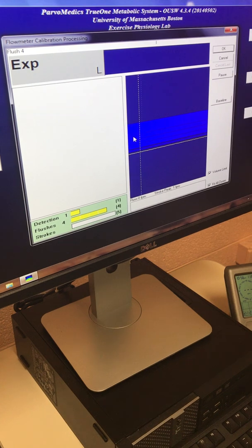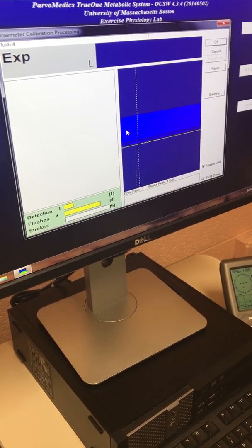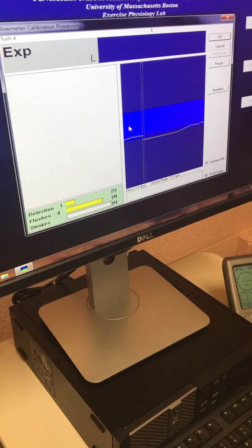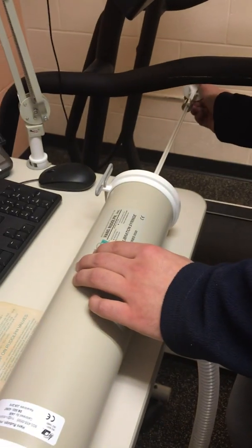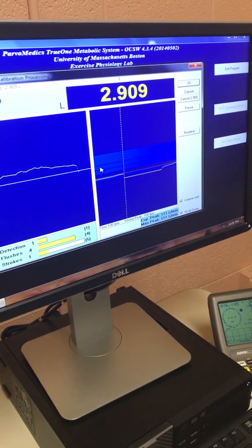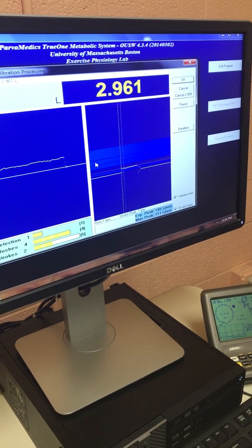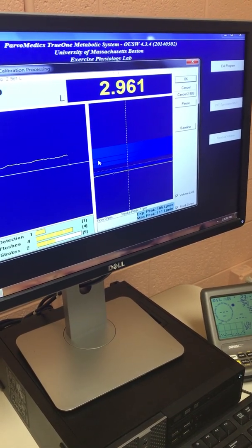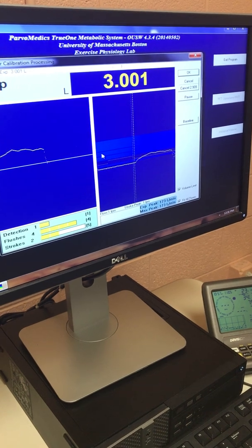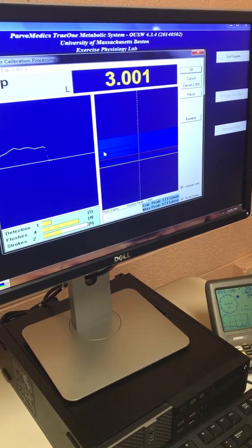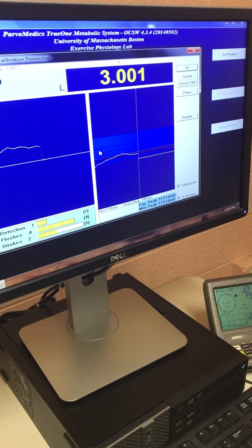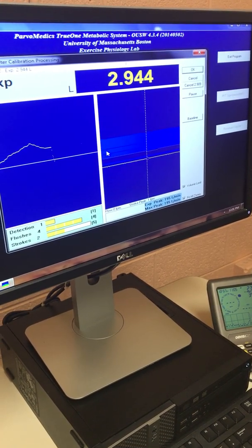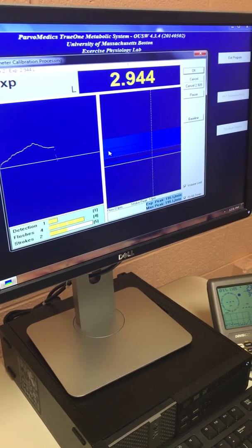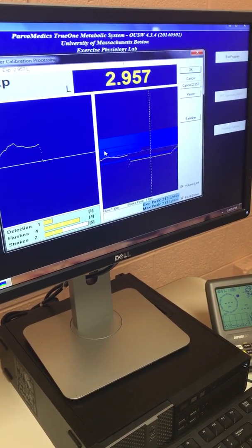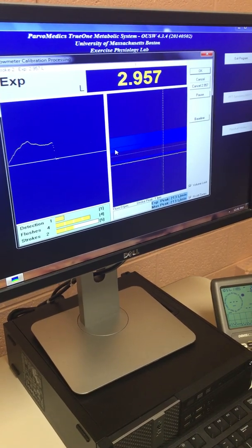And now we go to strokes, and we do 5 strokes, each of them increasing in magnitude until we get to the 5th stroke. And so on the screen, on the software program, we're going to hit the dotted line as we pull the syringe out and push it back in. And so it's going to let us know if we exceeded the threshold or if we need to perform another stroke. And sometimes it takes more than one attempt to reach the threshold.